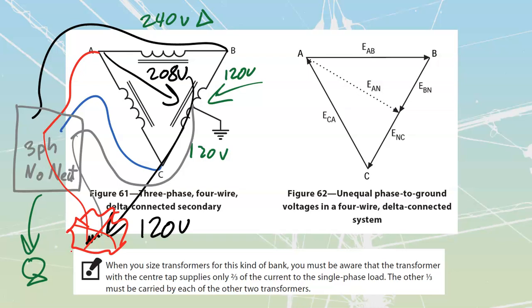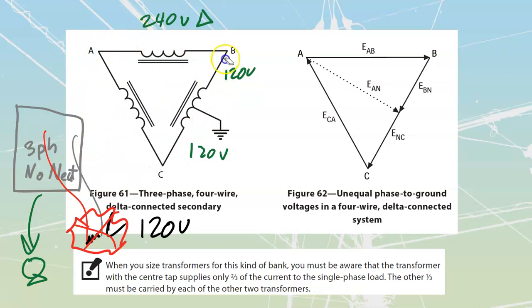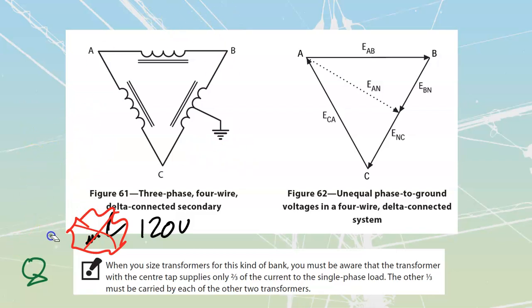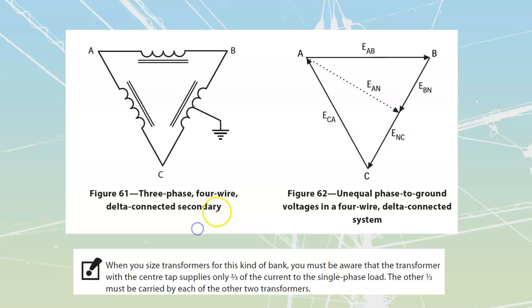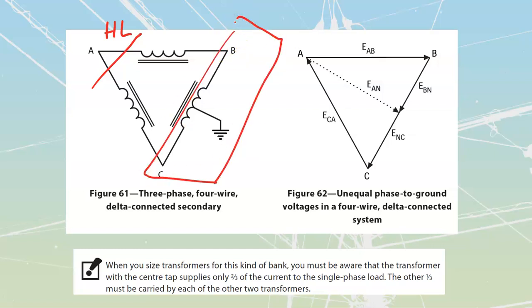The code book tells us that we have to make sure that this can't happen. First of all, anytime that one of these systems is used, we always have to make my A phase what they refer to as the high leg, or the leg that is furthest away from the neutral. So we'll call this one the high leg over here. And we have to make sure that this A high leg does not enter the same panel boards as the single phase connection that I'm going to take off of here.